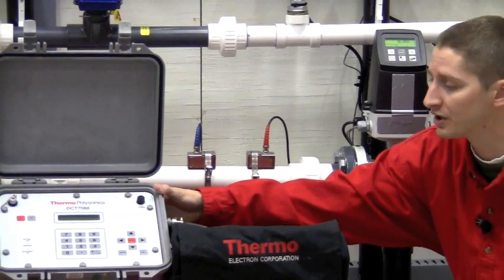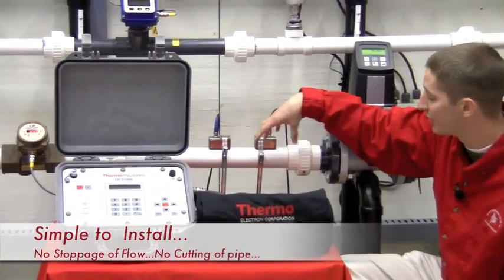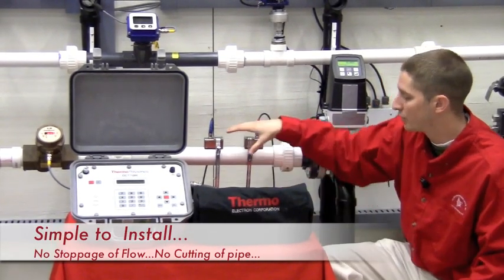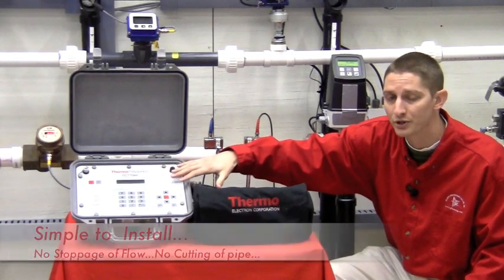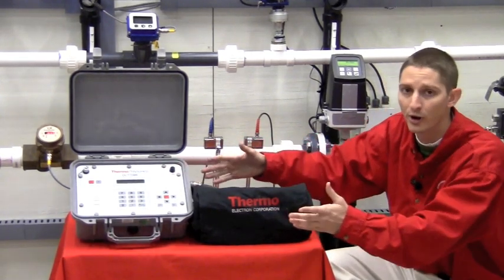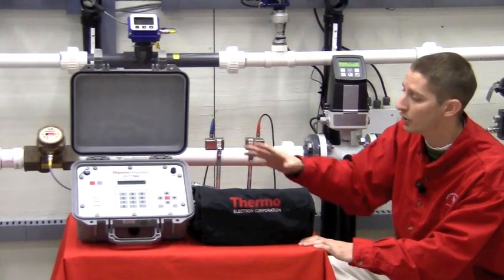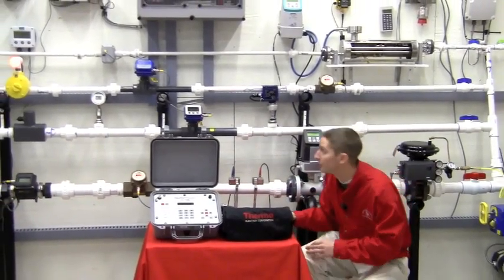With our Thermo Polysonics, all you actually have to do is mount your transducers to the outside of your line. There is no intrusion into your pipe. You have to provide power to this box, you're going to plug in a few parameters about your pipe, and then you're ready to measure flow. So what I'm going to do now is turn on our pump, and then we're going to show you the performance of this clamp-on versus this magmeter.